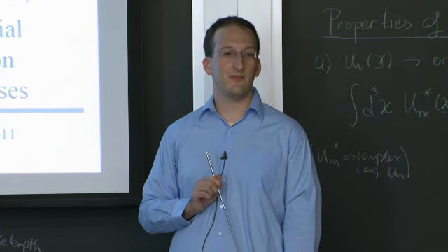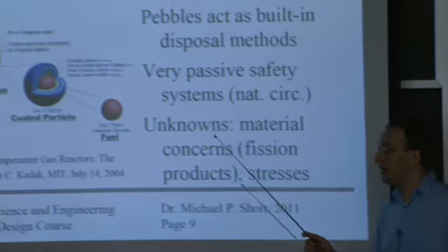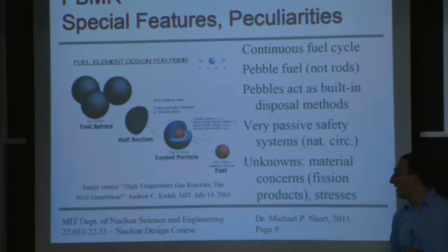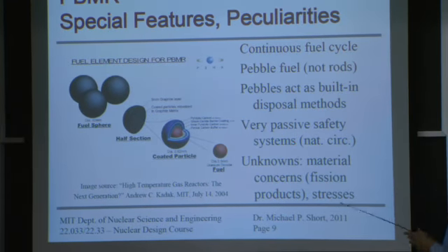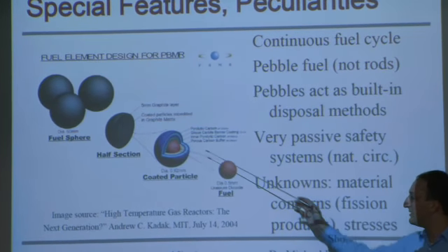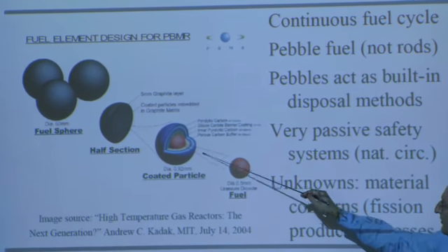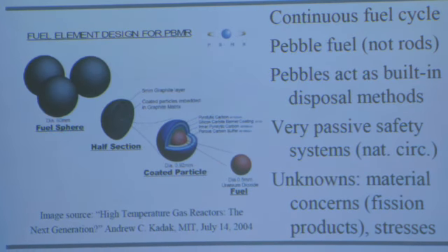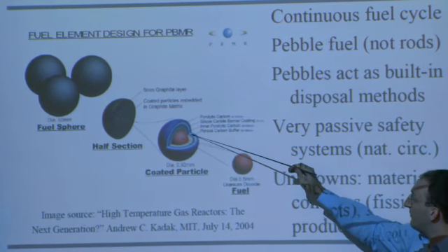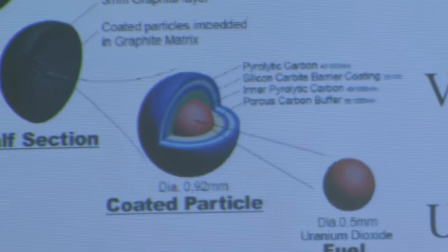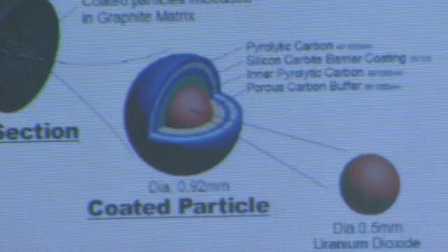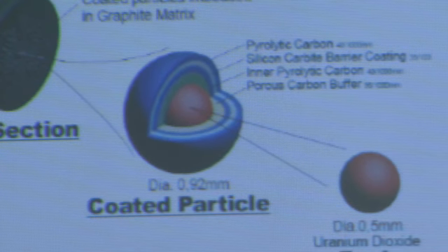The fuel for the pebble bed is not what you would recognize from a light water reactor. There are these what's called TRISO fuel spheres that are about 6 centimeters in diameter. And inside those are hundreds of thousands of tiny little kernels, these coated particles, less than a millimeter in diameter, that have an outer and inner layer of some pyrolytic graphite. It's kind of porous. The inner stuff helps absorb the fission products. There's a layer of, right now, silicon carbide, which acts as the barrier to, one, keep everything inside the pellet from getting out, and two, that's sort of the stress holding layer.